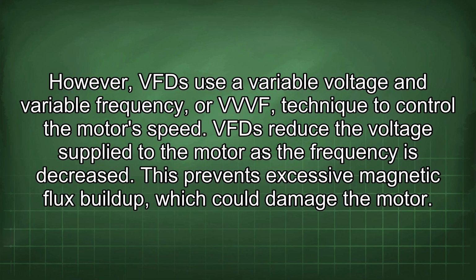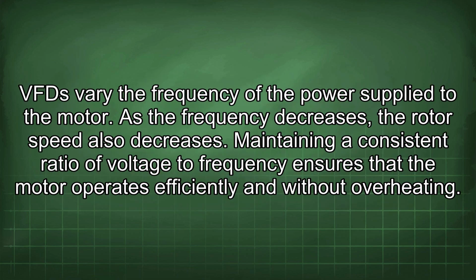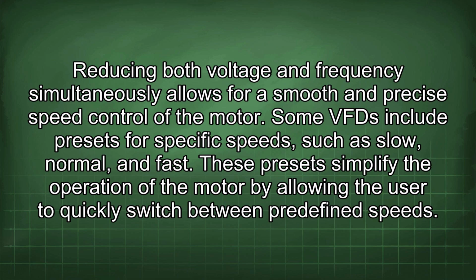VFDs reduce the voltage supplied to the motor as the frequency is decreased. This prevents excessive magnetic flux buildup, which could damage the motor. VFDs vary the frequency of the power supplied to the motor. As the frequency decreases, the rotor speed also decreases. Maintaining a consistent ratio of voltage to frequency ensures that the motor operates efficiently and without overheating. Reducing both voltage and frequency simultaneously allows for a smooth and precise speed control of the motor.